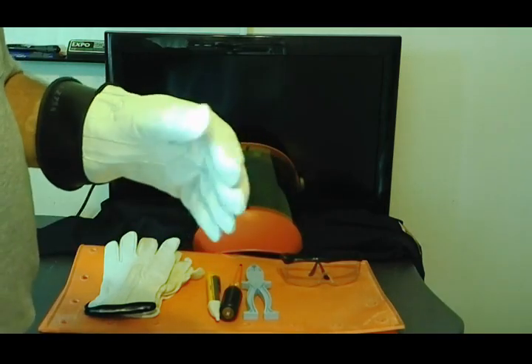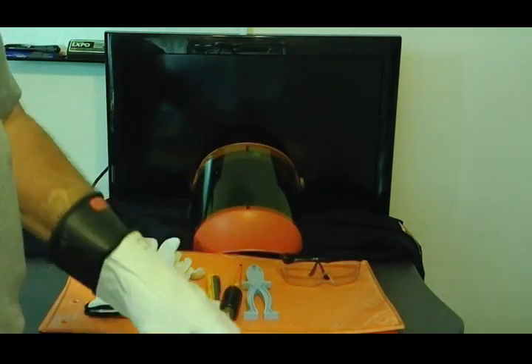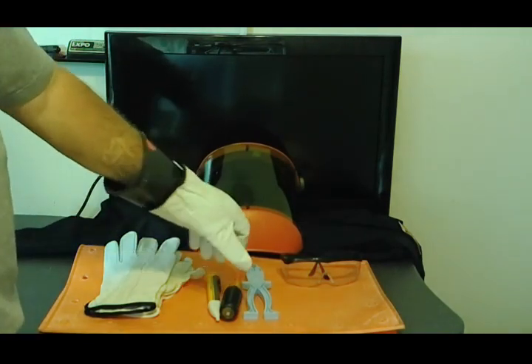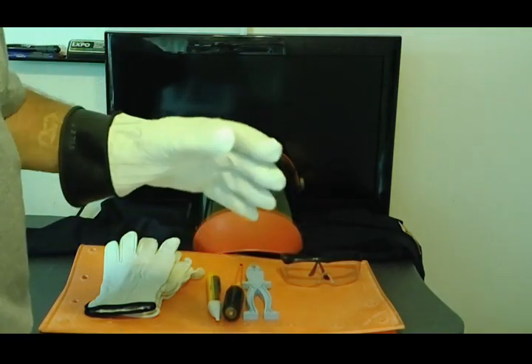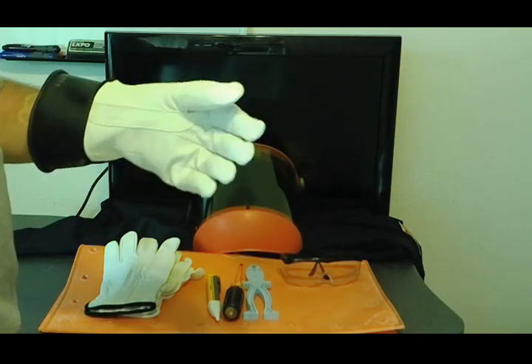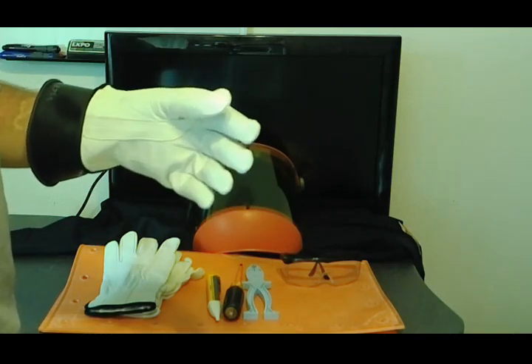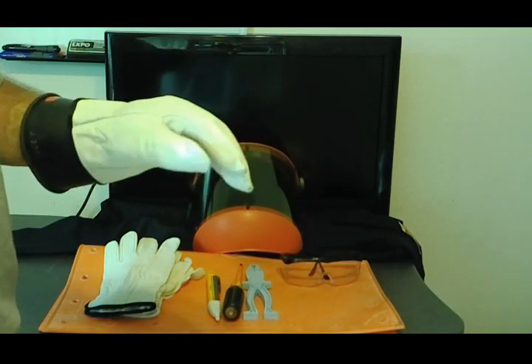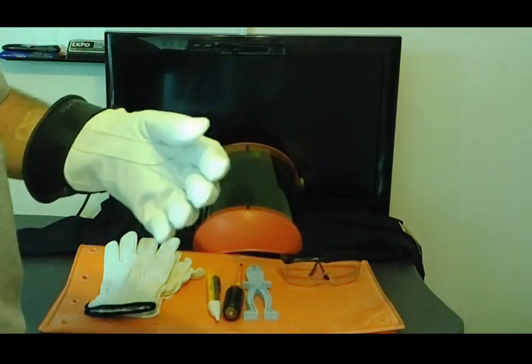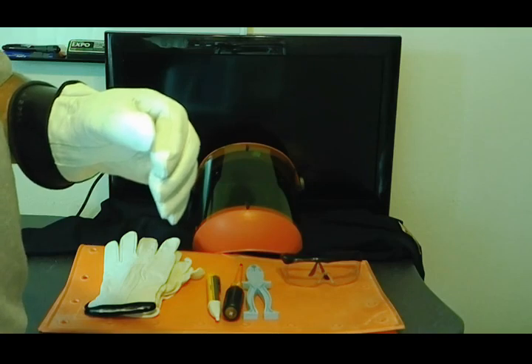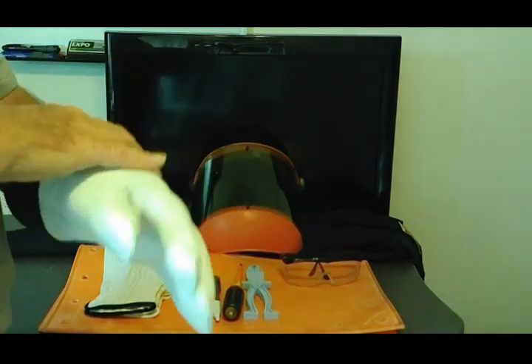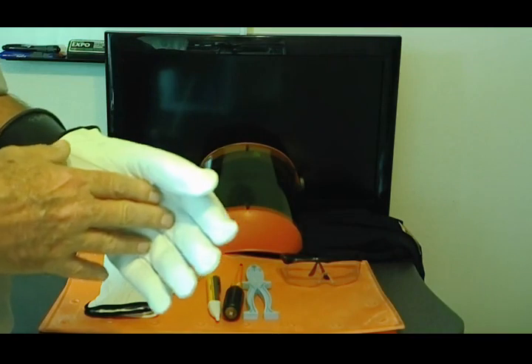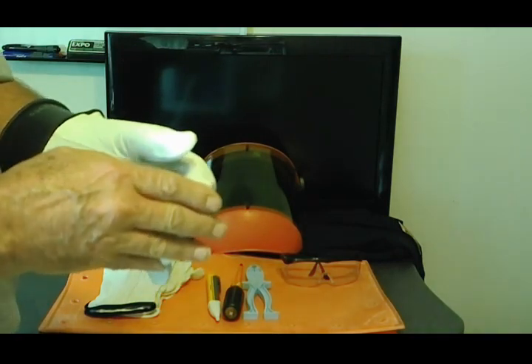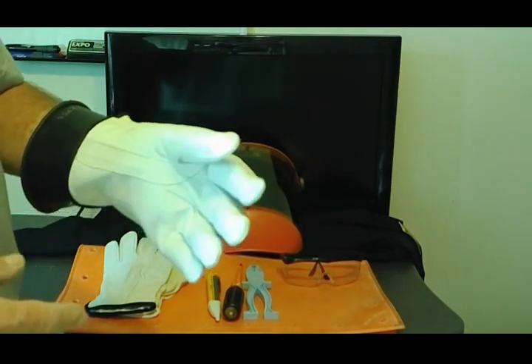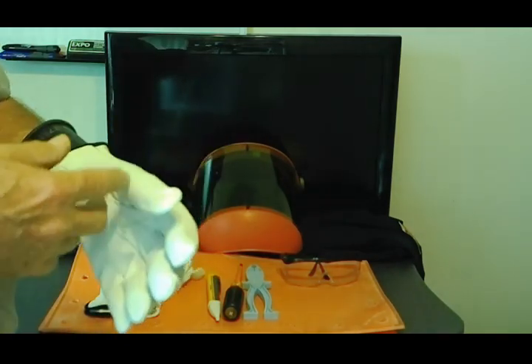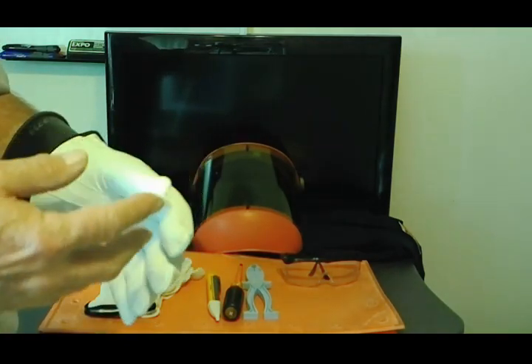Now there's a lot of times people complain it's cumbersome, you can't pick anything up, it's hard to work with these things, and that is true. Once you put a glove on, your hands are a lot stiffer. The rubber takes up a lot of space, making things thicker, and they are cumbersome to use, but there's a key to this: you get the size of the rubber glove and leather glove that fits your hand. If the glove is too big, it's going to be hard to work in. If the glove is too small, it's tight and it hurts you. So you need to have the size that fits you.